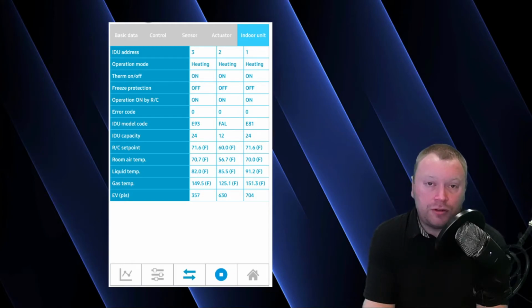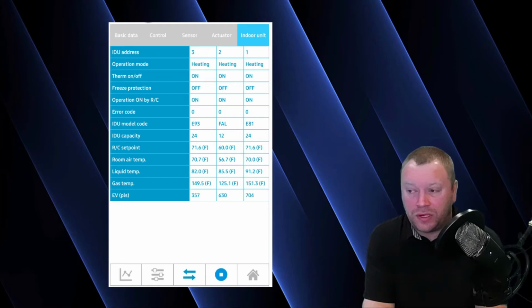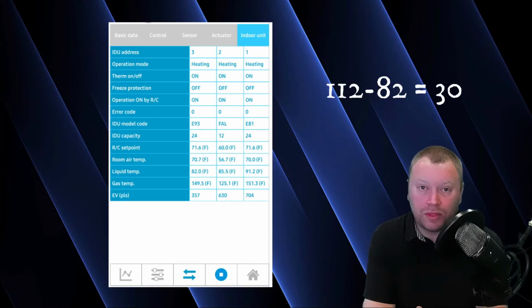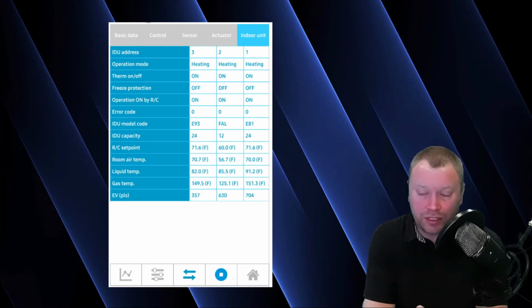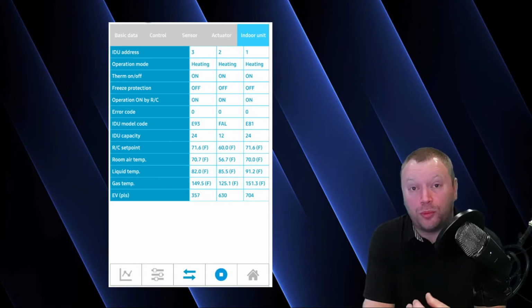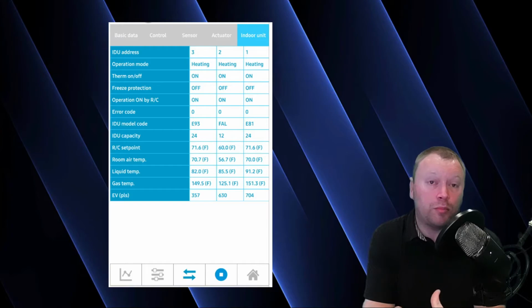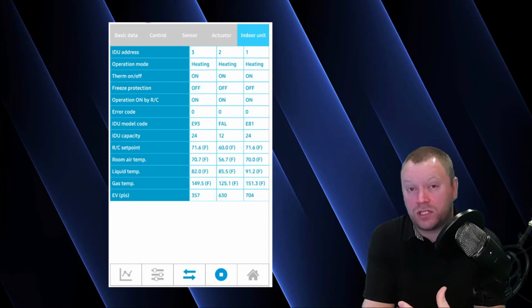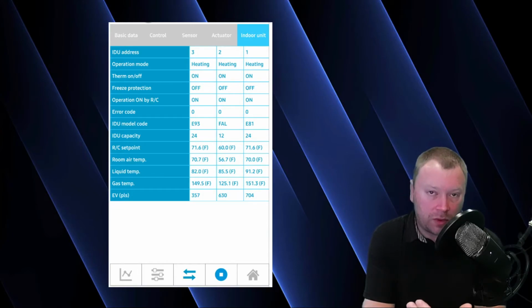So if I have a 112 degree condensing temperature, you can see that unit number 3 has a rough subcooling of 30 degrees. That isn't really a good amount of subcooling. Again, this is just a snapshot. So what I anticipate happening over the next few minutes is that EV position is going to open up. When the EV opens up, it brings down our subcooling. If our subcooling was too low, we weren't getting enough, then that EEV is going to throttle down to increase the amount of subcooling that we have.